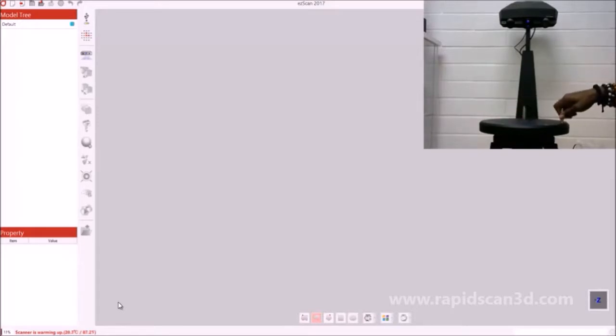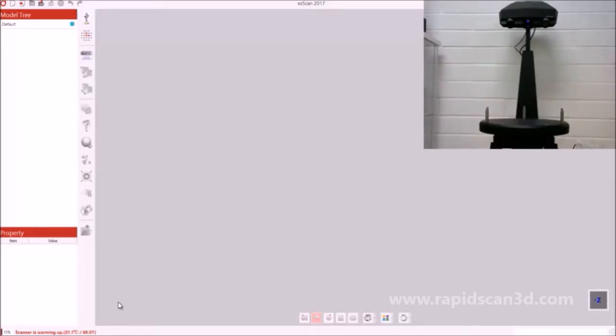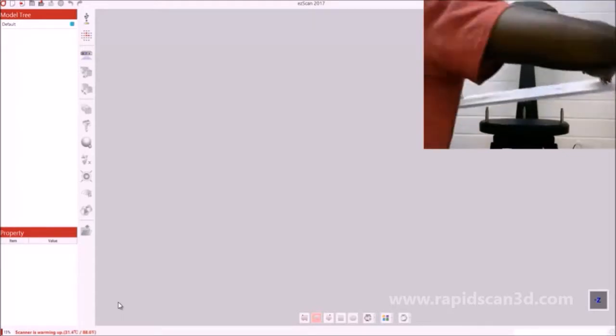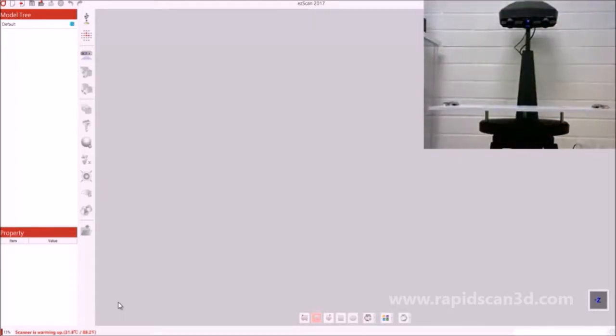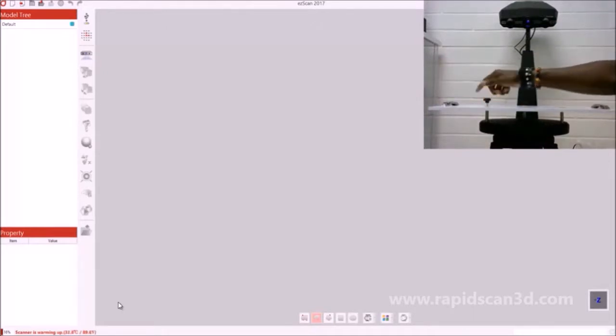In the meantime, while the scanner is warming up, we're going to set up the calibration plate, which involves putting down three screws and then putting the calibration plate on top of those screws.